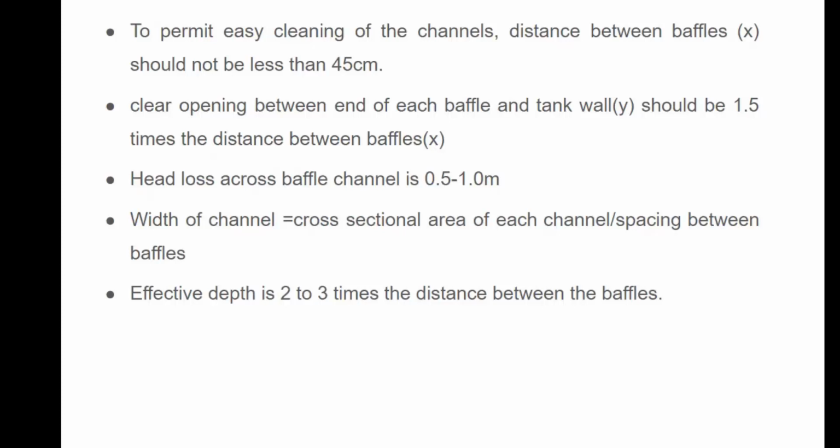That is, from the tank wall, there should be a gap between the baffle walls. That should be 1.5 times the distance between the baffles. The distance between the baffles will not be less than 45 centimeter. Then multiplying by 1.5 will give the distance between the wall of the tank and the end of the baffle.